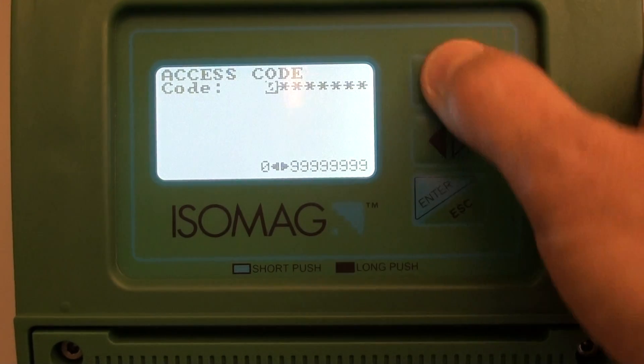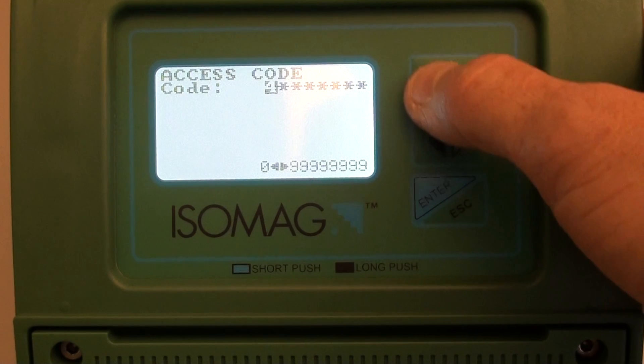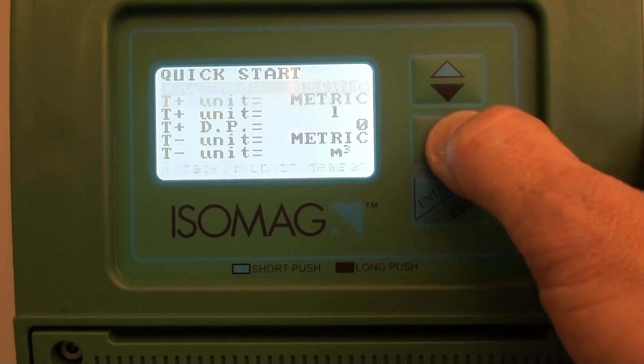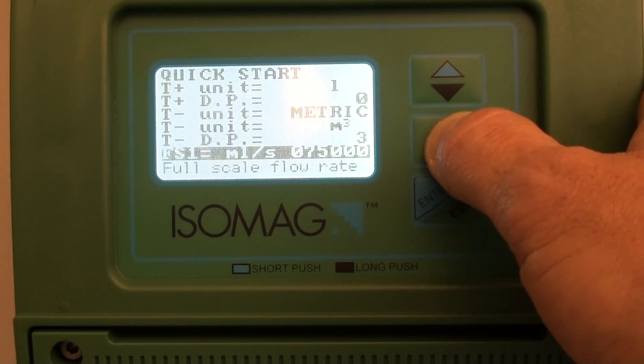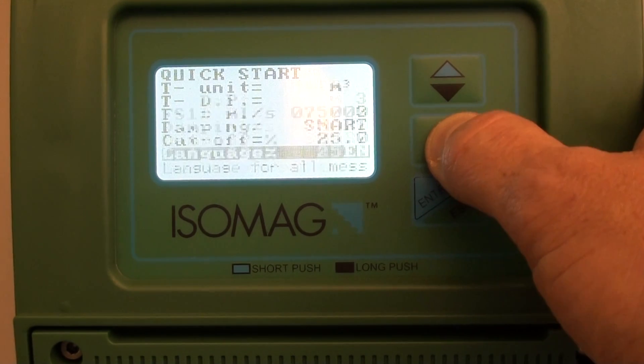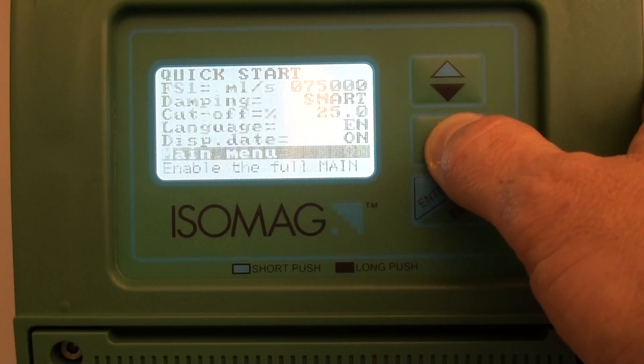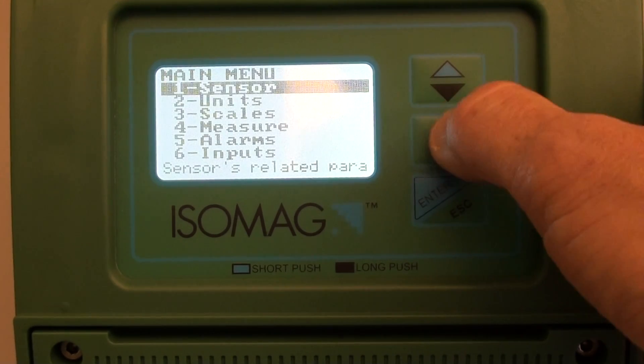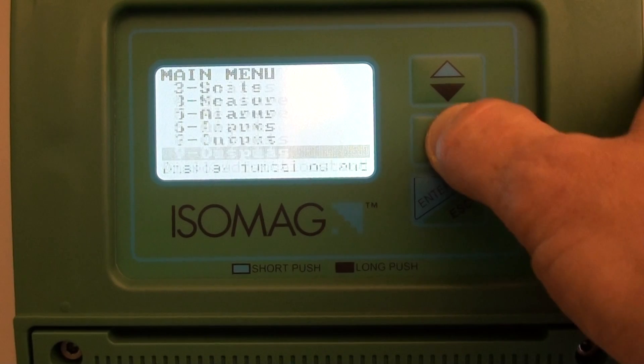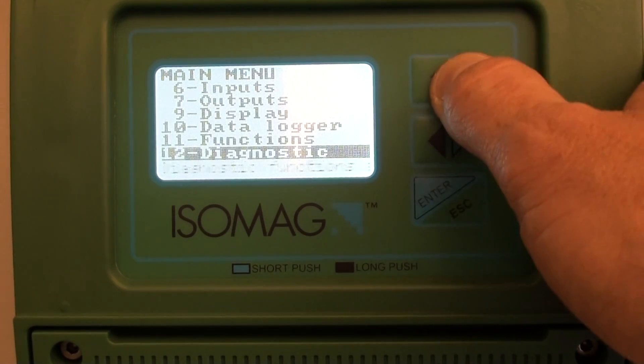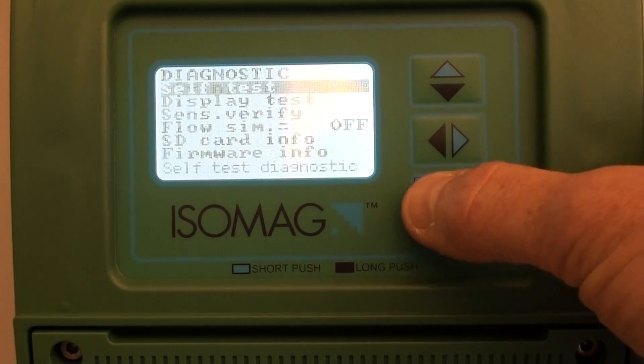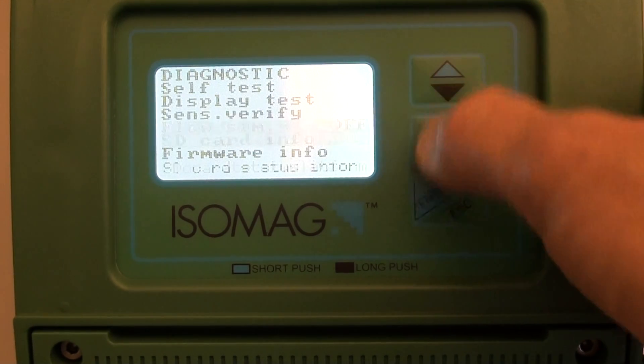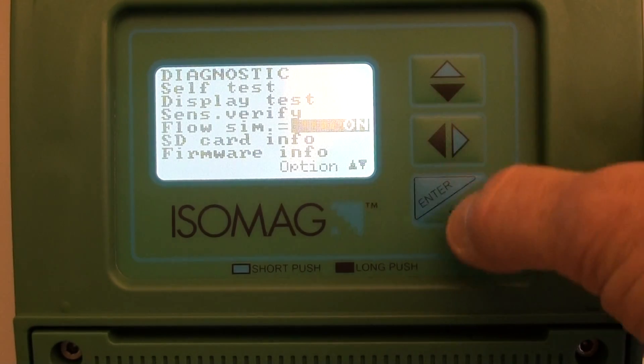We can reach the flow rate simulation function by inputting the level 4 access code. We may find it in the quick start menu if it has been selected to be visible, or we need to go into the main menu system to the diagnostics menu, menu 12, and go to flow simulation and enable it.